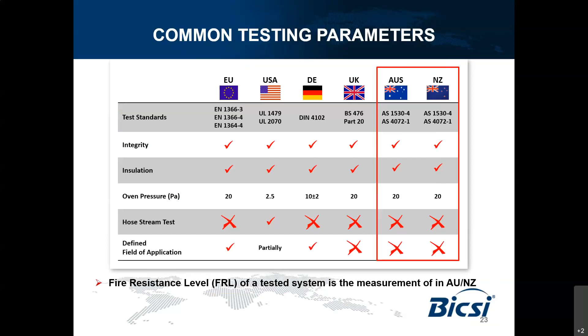The first digit refers to structural adequacy, which is about whether the wall can take loading. The second number refers to integrity, which is about the flame and hot gases passing through the barrier. The third is about insulation, which is about temperature, making sure that the fire side and non-fire side have no heat transfer, or only limited heat transfer.